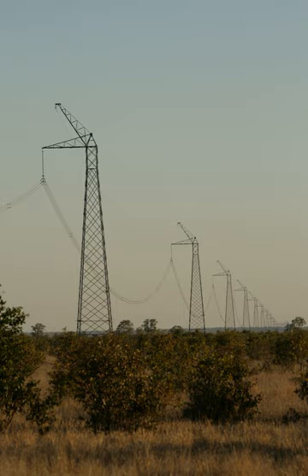Modern systems install spiral vibration dampers on the wires. Insulators are often porcelain because polymers are prone to ultraviolet damage. Some utilities install higher voltage insulators so the line can be easily upgraded to carry more power — for example, 12 kV lines may be insulated to 22 kV, or 19 kV lines to 33 kV. Reinforced concrete poles have been traditionally used in SWER lines because of their low cost, low maintenance, and resistance to water damage, termites and fungi. Local labor can produce them in most areas, further lowering costs. In New Zealand, metal poles are common, often being former rails from a railway line.